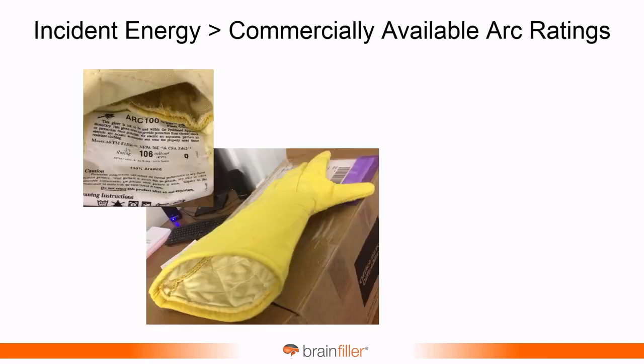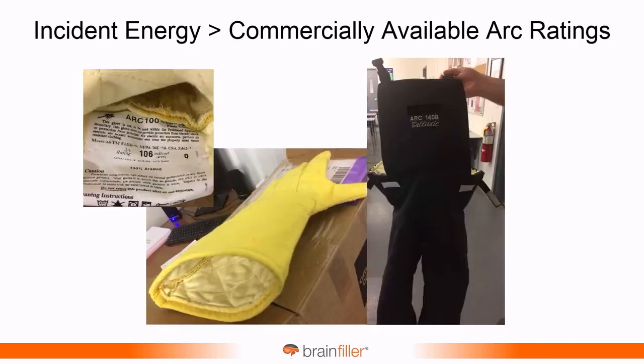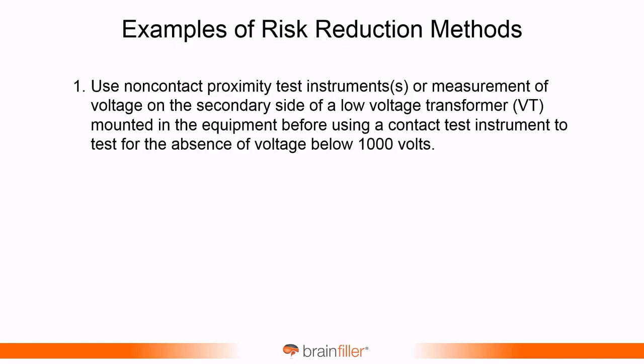First off, I want to mention PPE. The arc ratings have been going up considerably. This one on the right, that's actually my hand holding it up. It almost stood up by itself. This is an arc rating of 140 calories. And so arc ratings continue to increase, but not everybody has access to this kind of PPE, and you can still have incident energy levels above these values. So what are the risk reduction methods?